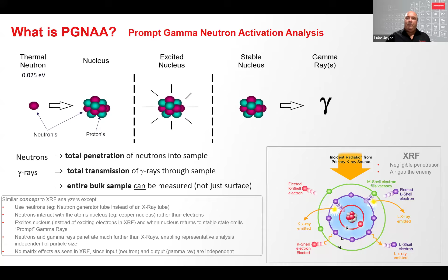One of the key differences with PGNAA is that both neutrons and gamma rays can penetrate entire rocks and sample depths up to hundreds of millimeters, compared to only a few microns of penetration for X-rays. So it can provide representative analysis of large volumes of material independent of particle size. Another key difference is that there are no matrix effects as seen in XRF, since in PGNAA the input, neutrons, and the output, gamma rays, are independent, whereas in XRF, an X-ray emitted from a heavier element, higher than calcium on the periodic table, can excite lighter elements lower on the periodic table before reaching the detector, which impacts the detected X-ray spectrum and often requires recalibration for changes in mineralogy. PGNAA doesn't suffer the same issue with changing mineralogy.